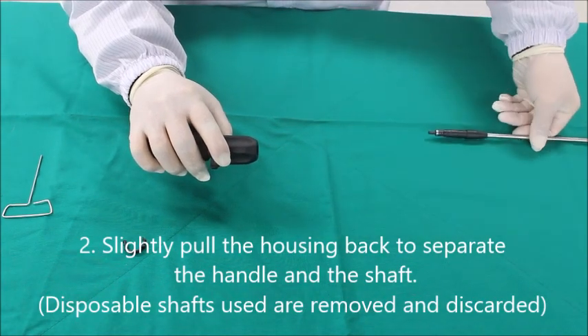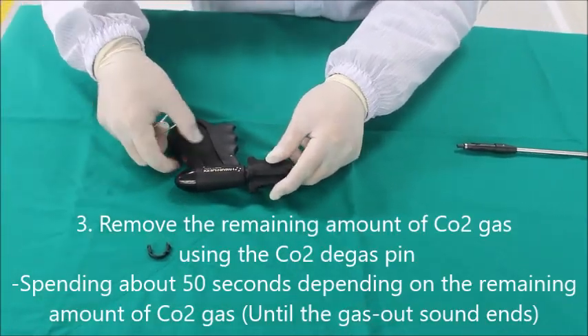The shaft is single use only. Discard the used shaft in accordance with the medical waste regulations.